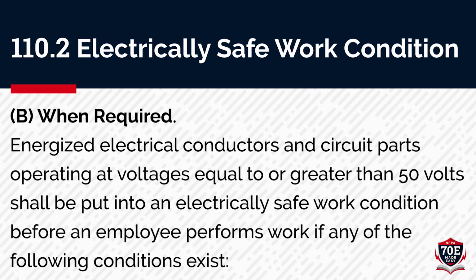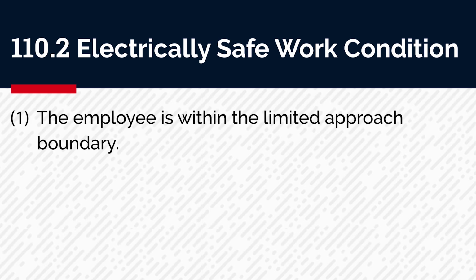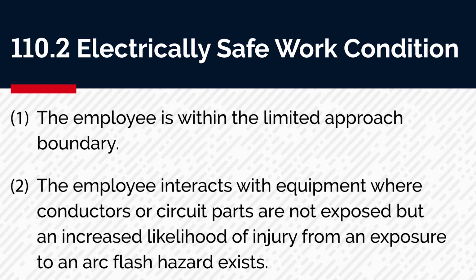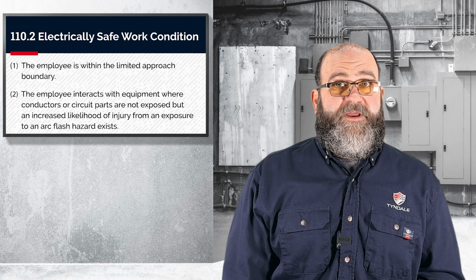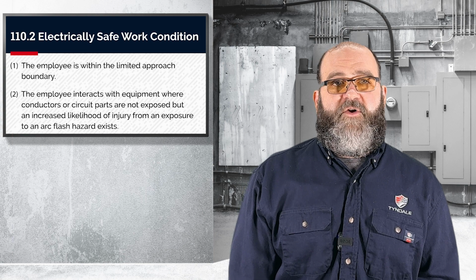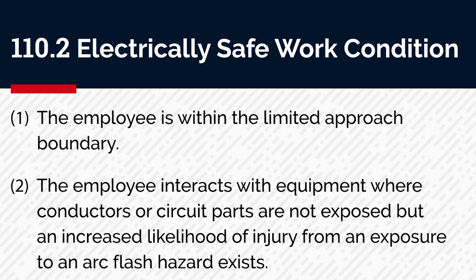110.2B says, when required, energized electrical conductors and circuit parts operating at voltages equal to or greater than 50 volts shall be put into an electrically safe work condition before an employee performs work if any of the following conditions exist. Number one, the employee is within the limited approach boundary. Or number two, the employee interacts with equipment where conductors or circuit parts are not exposed, but an increased likelihood of injury from an exposure to an arc flash hazard exists. And just to reiterate, this is at any voltage 50 volts and greater. More on that later. But right now I want to focus a bit on the second item, which was interacting.